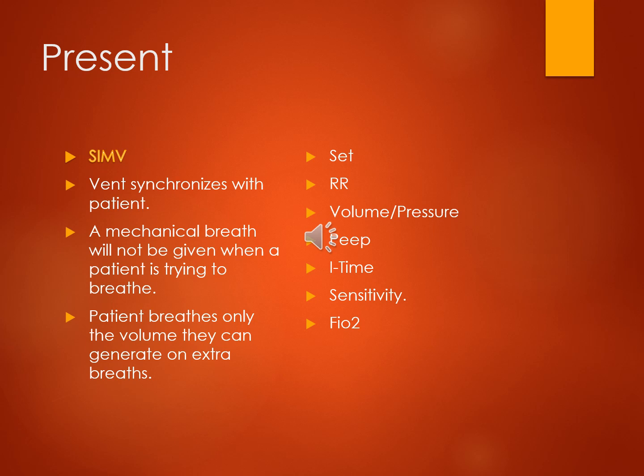So if the patient decided to start taking a breath at 5.5 seconds, the ventilator doesn't care and it would step on their breath. Well, synchronized intermittent mandatory ventilation synchronizes the ventilator. So if it sees you or feels you or senses you taking a breath, the ventilator will not add its breath on top of your breath. So that's a really nice safety feature, right? It protects the airways and decreases the likelihood that the ventilator is going to step on the patient's breath and add too large of a volume to their breathing pattern.